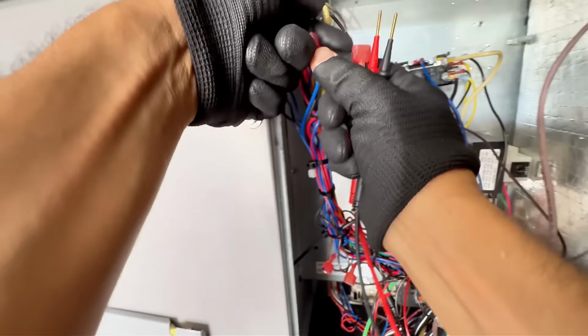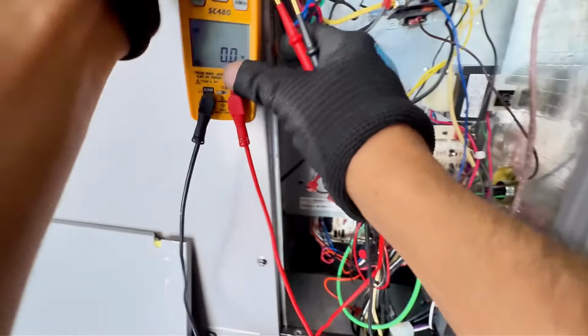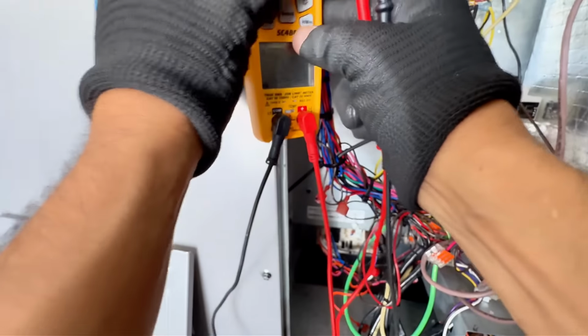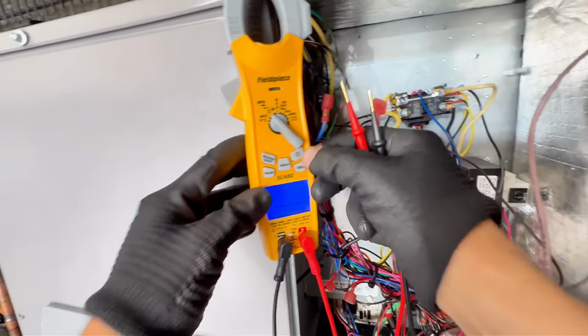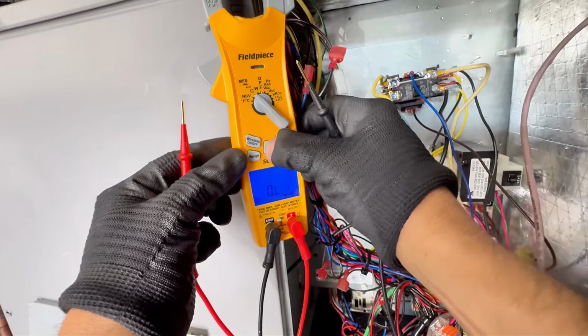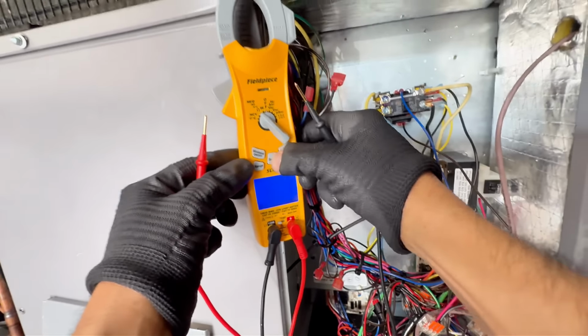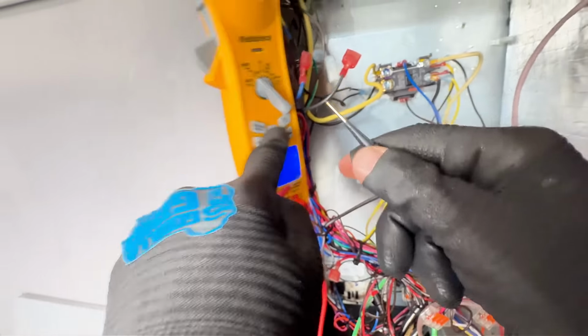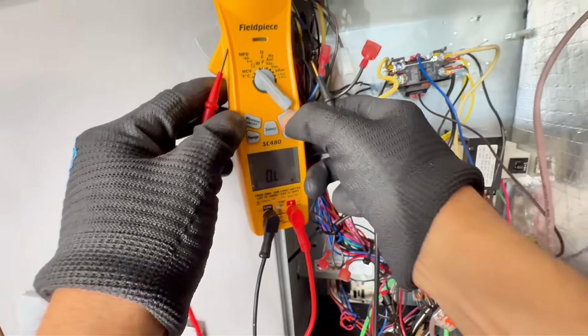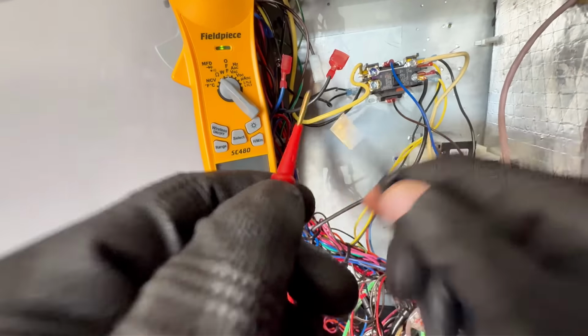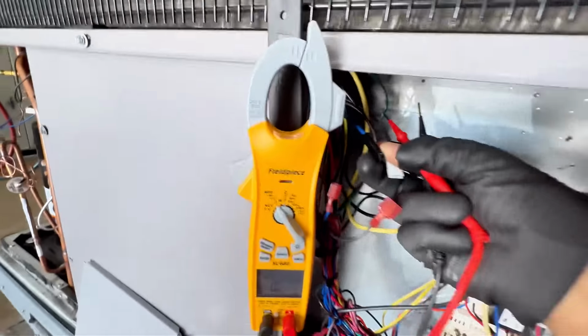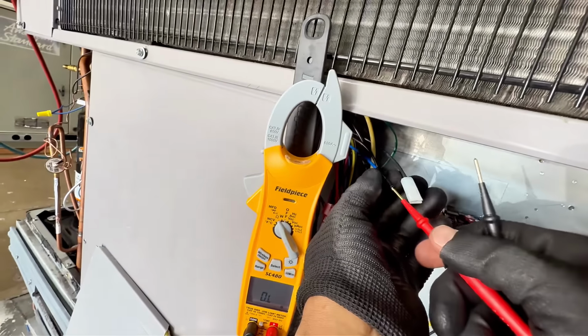What I'm going to confirm, an easy way to make sure your pressure switches are closed, you can just disconnect these right here. Okay. Put it on continuity. So let's go ahead and put that on continuity. Okay, just check it. You see that? Continuity. So I'm going to go ahead and check the path going to my pressure switches, it should be closed.